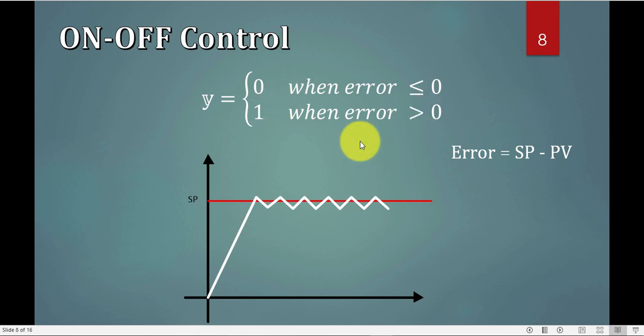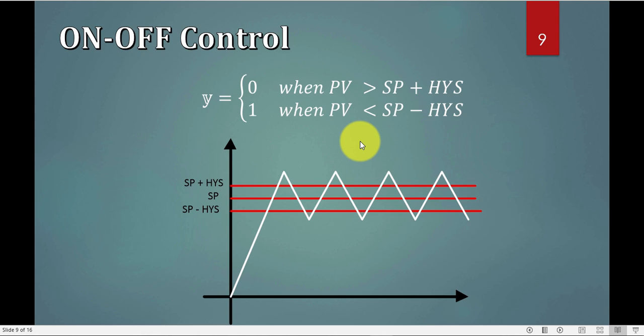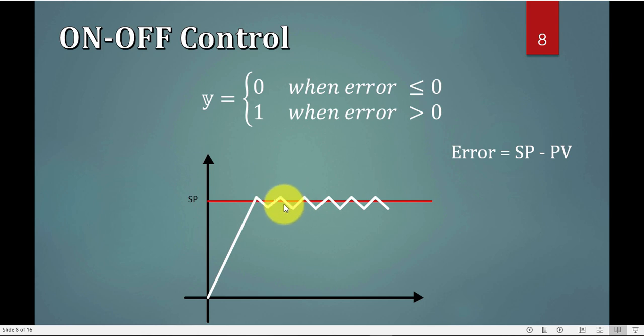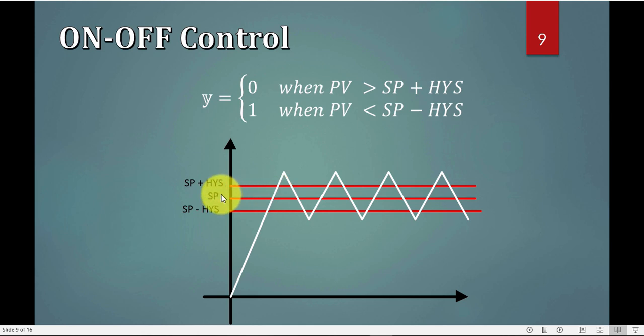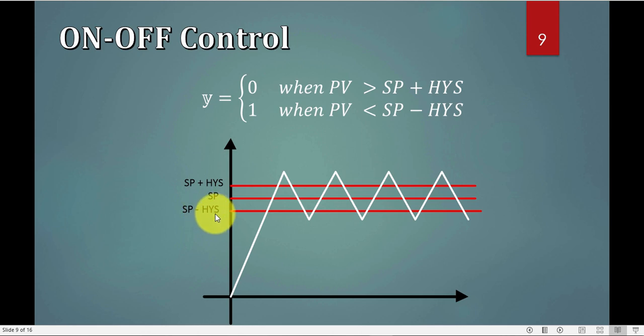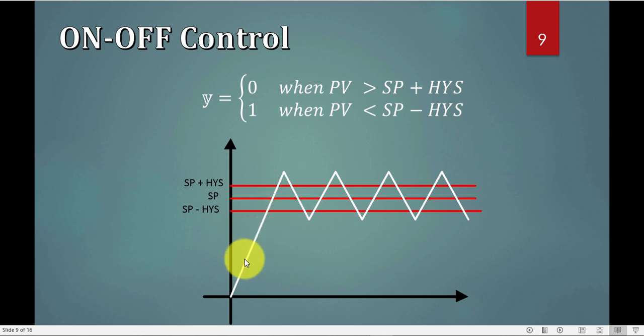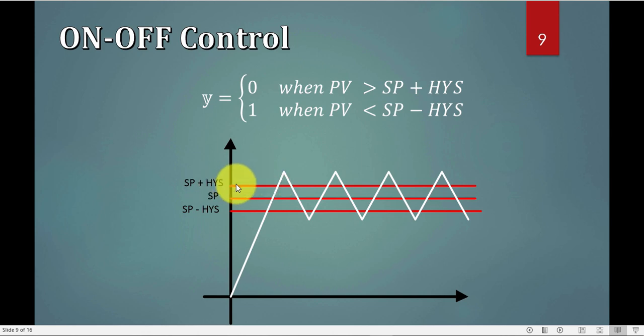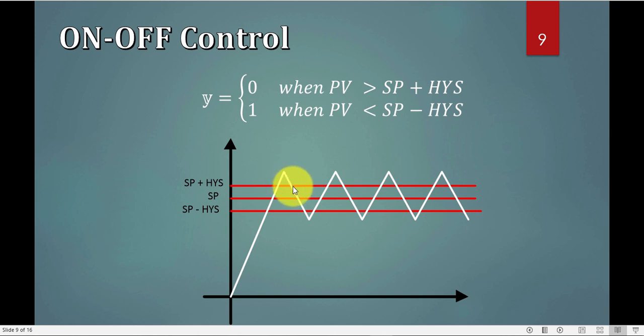Now, about the hysteresis, for the next slide, I will add, as you saw here in the previous one, it's really a lot of on-off, this will stress my actuator. But if I add another value, set point plus hysteresis, and one below the set point is set point minus hysteresis, so my PV, the white curve, if it is less than the set point minus hysteresis, it will be one, so my controller will be on, and it will latch on, and it will only turn off when the PV is higher than the set point plus hysteresis.